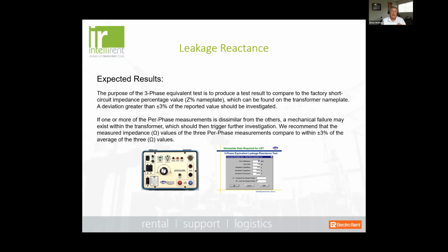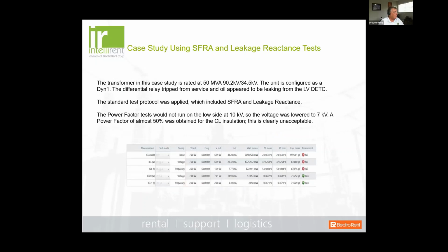Okay, you may not have a through fault monitor in your protective relaying system active. So this would be your first line of interrogation to see if those through faults have caused damage, or if your through fault alarm has given an indication that you've had excessive through faults or one high through fault, and so on and so forth. So leakage reactance can be your preemptive test to the SFRA, because if leakage reactance comes out okay and all your subsequent tests come out okay, then SFRA in all likelihood will not be necessary. Okay, so let's take a case study here.